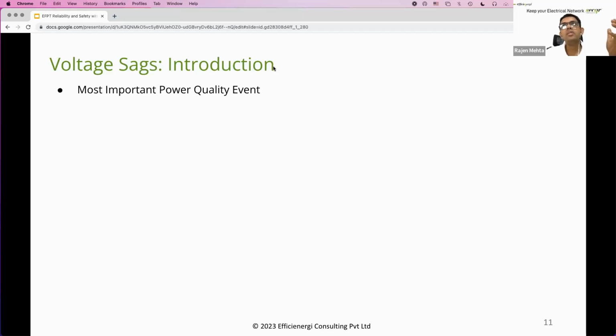Now let me tell you that voltage sags are the first and most important power quality event. Why? Because 70% of the problems occurring within a facility due to power quality are caused by voltage sags - out of all power quality events, voltage sags are the number one cause of damage to sensitive equipment. By sensitive equipment I mean variable frequency drives, servers, UPSs, CNCs, anything nonlinear or sensitive in nature, including laboratory equipment like liquid chromatography in pharma R&D labs. That's where voltage sags are most prevalent and cause the maximum damage.